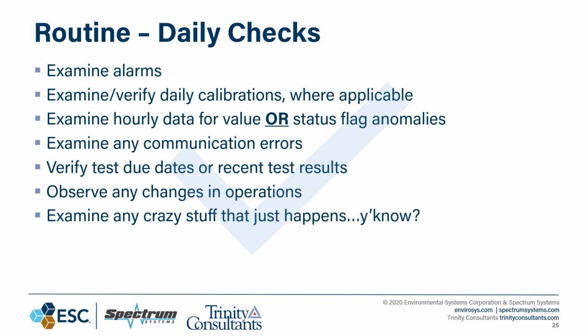That's very true. When we're going out for auditing purposes, conducting mock audits, part of our routine is to actually ask questions. What does your daily routine look like? What are you looking for? How often are you training on this stuff? What would you generally identify as a problem in the system at its most base level? Show us how you do your jobs. What are you looking at on a daily or weekly basis to verify the operation of these systems, that everything's looking normal? Are we talking about a cold dry extractive system here, or a dilution extractive system?